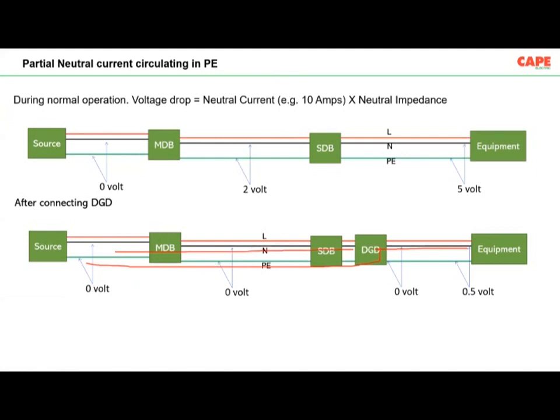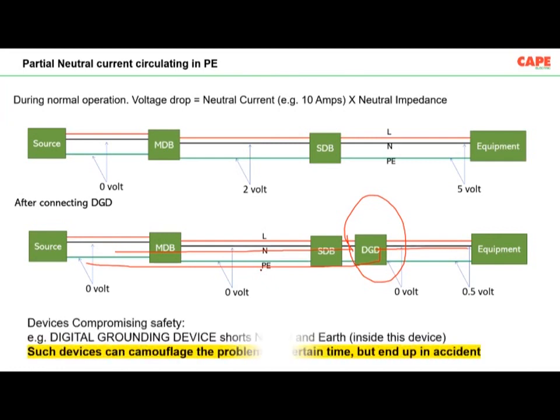Imagine your neutral current is 10 ampere, but after connecting this particular device, about 5 ampere flows through your earth conductor, but our maximum allowed current is, let us say, for example, 10 milliampere. So you are actually violating the electrical safety system. Now, these kinds of devices or any shorting between neutral and earth in an installation is deadly. Please don't do it. You can connect neutral to earth only at one place, strictly at the source. After that, your neutral and earth must be separate. If you make any connection, then your earthing is gone. Continuous current flow will happen through the earth conductor. As a result, you will have fire, you will have electromagnetic problems, you will have a short circuit, and basically you will end up with an accident.